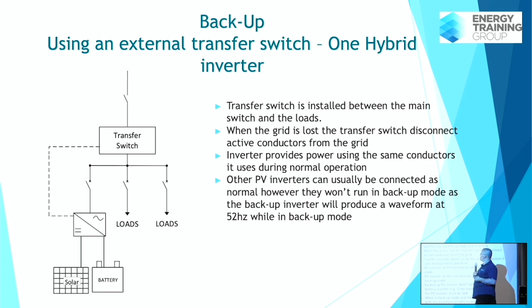Now, one thing that's really important with AC coupled systems is that if I have a 5 kilowatt battery inverter, in backup mode, it can only charge at 5 kilowatt. So a 5 kilowatt inverter can only accept 5 kilowatts coming into it, as well as put 5 kilowatts going out. So if I had a system that could start a grid-tied inverter while in backup mode, I can't install a 5 kilowatt battery inverter and then install a 10 kilowatt solar inverter next to it. Because when I go into backup mode, my 10 kilowatt inverter is going to overload my battery inverter. There's nowhere for the current to go. Usually when there's excess current, it goes to the grid. You're off grid.